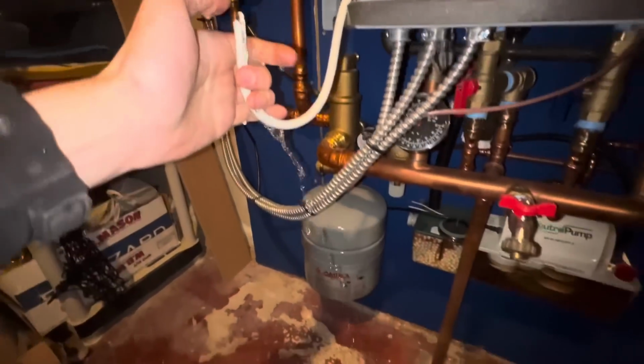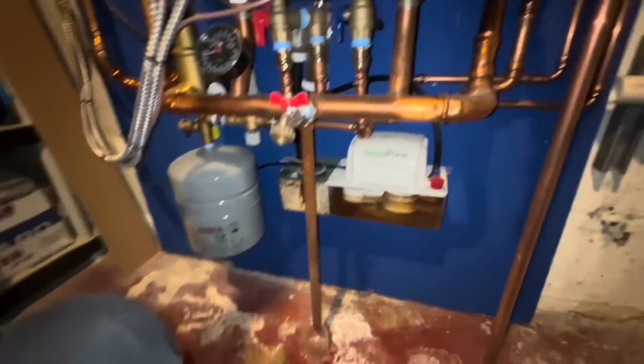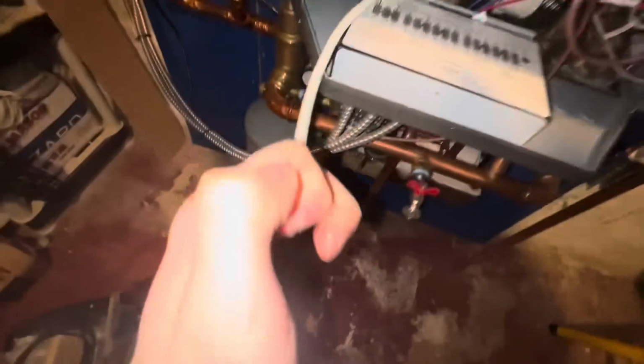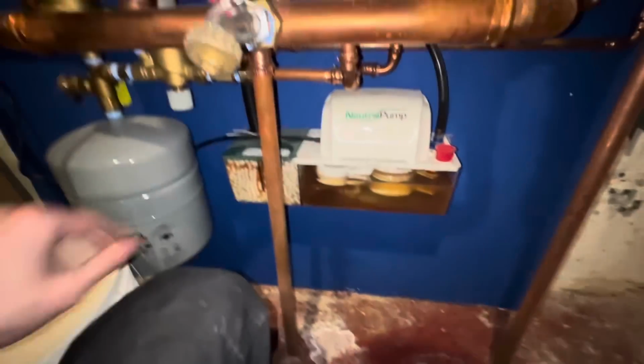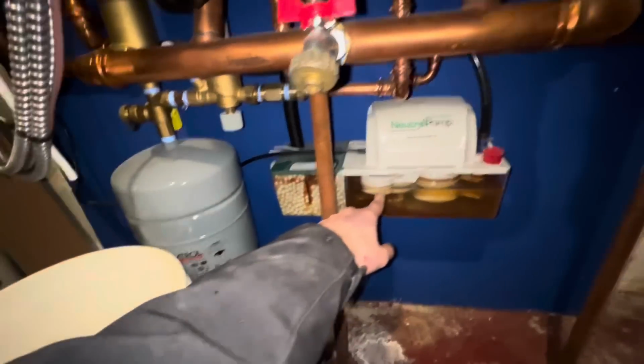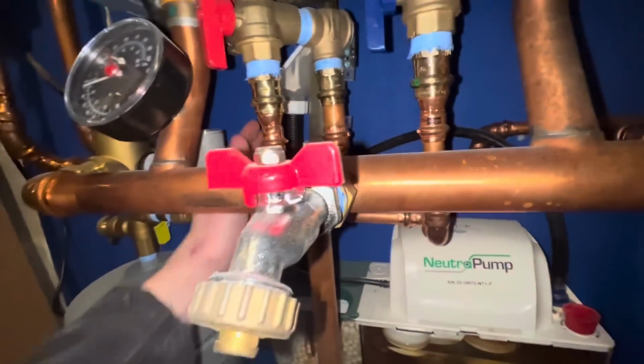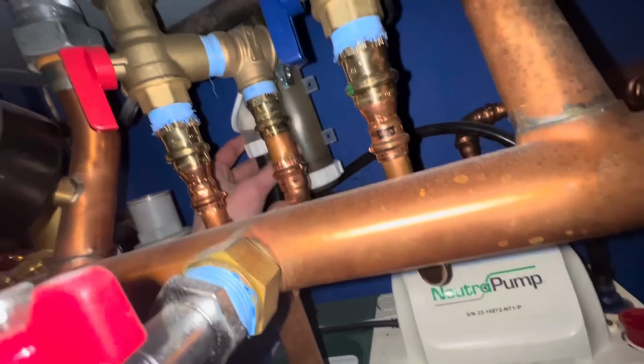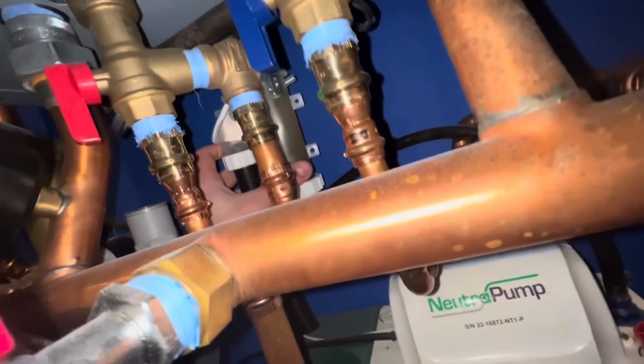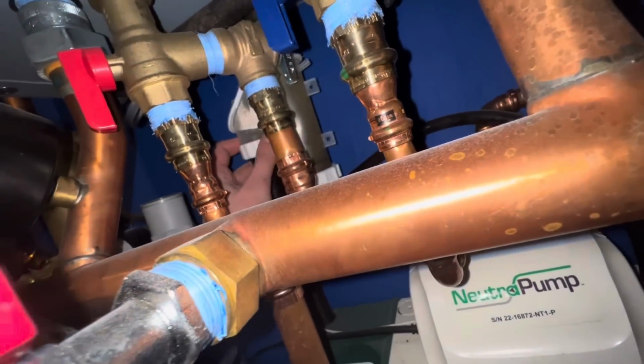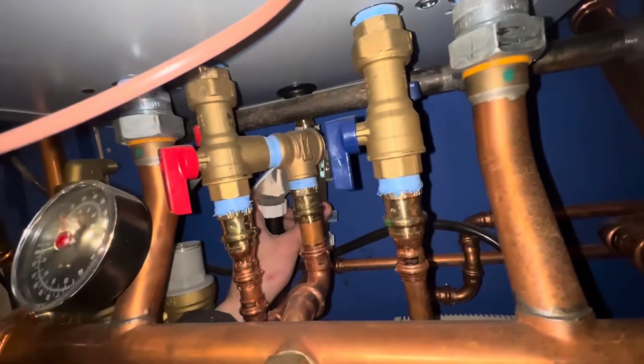Let's see if I disconnect this pressure switch here. And we are full of water. So we got a clog in our condensate line. Why? I'm gonna investigate. The pump, it's not gonna pump right now because it's not full up to the float. Yeah, I was gonna say, I've seen it actually work. Yeah, what's happening is we're not draining before the pump. Why? I don't know, but we'll take it apart and see.